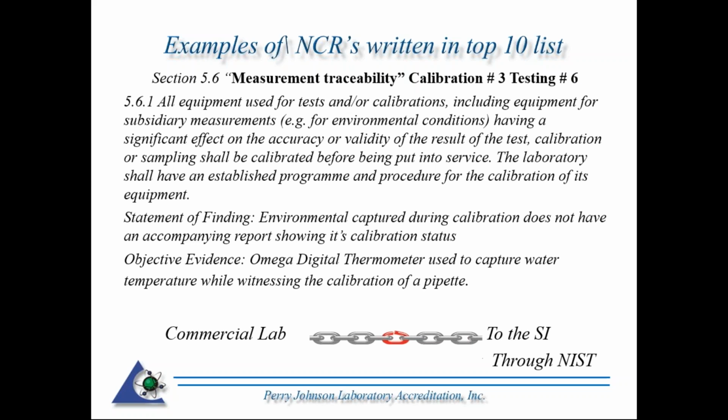The objective evidence that was looked at was an actual thermometer used to capture water temperature while witnessing the calibration of a pipette. Those folks that are in the calibration of pipettes would know that's a significant piece of equipment used in the calibration of pipettes, because you're correcting for temperature and you're also converting mass to a volume, and the temperature of the water is captured and utilized in that calculation. So it's not just your physical standard, your equipment. Bear in mind, it's also anything that you're using to capture your environmentals. If you're putting the environmentals on the report, chances are it needs to be calibrated. It needs to be a traceable calibration.